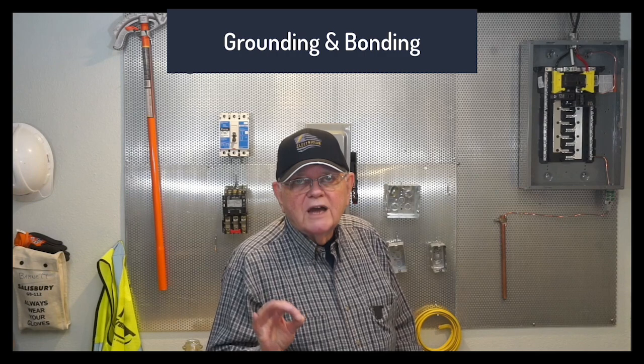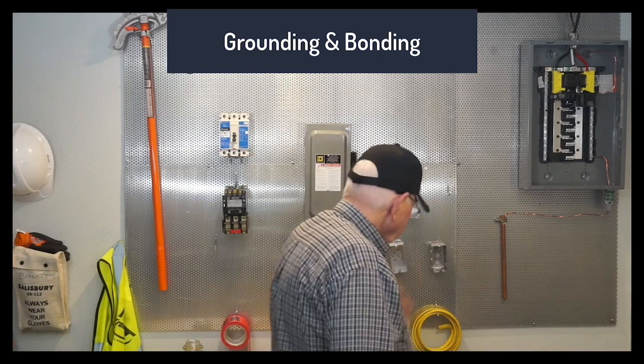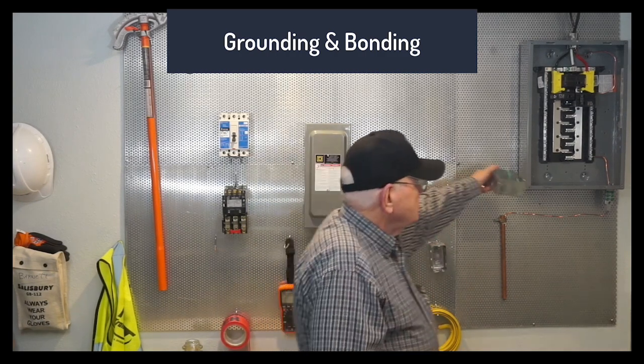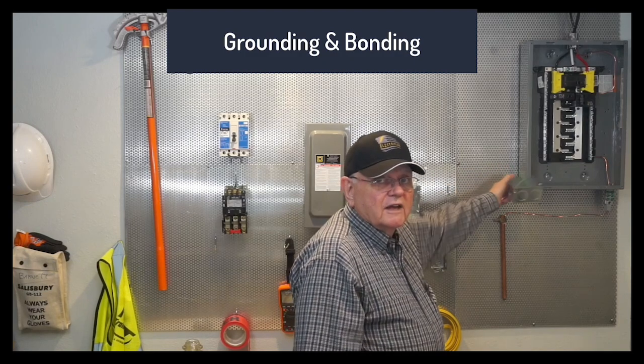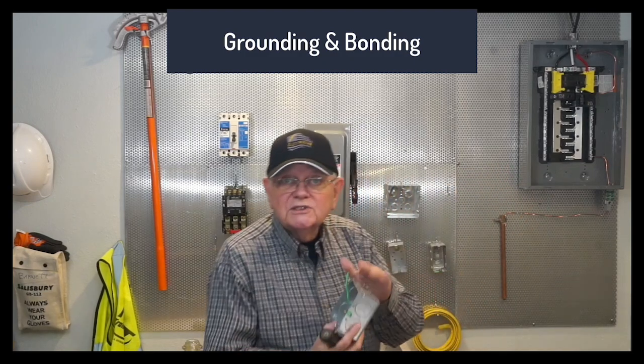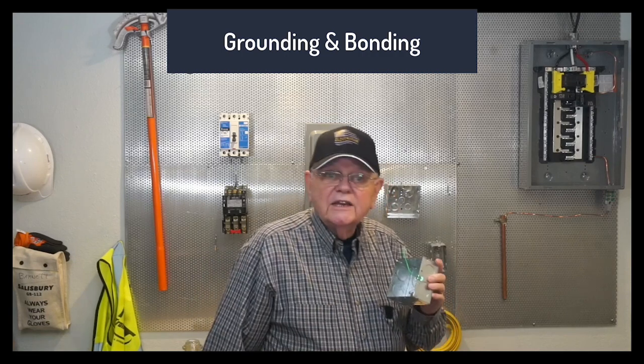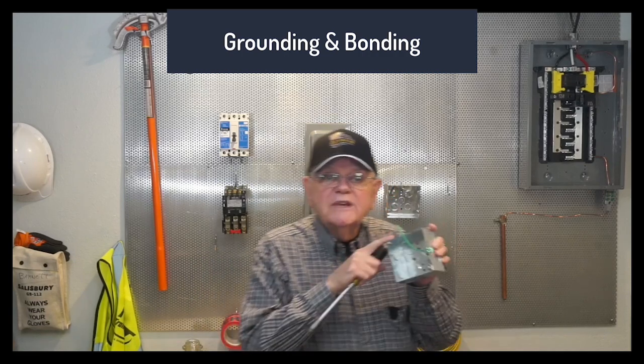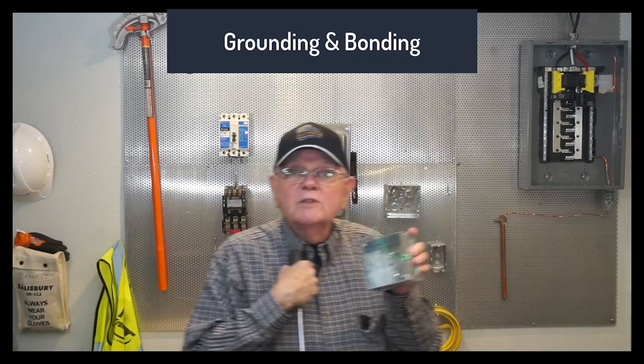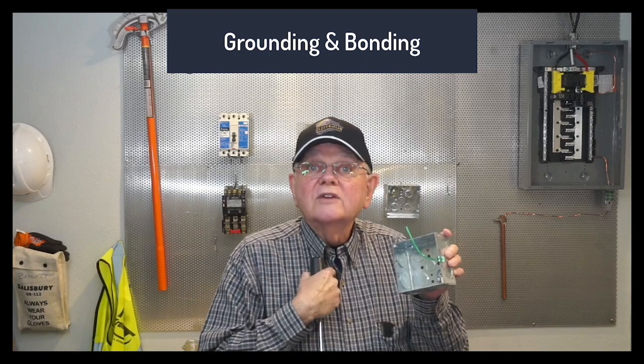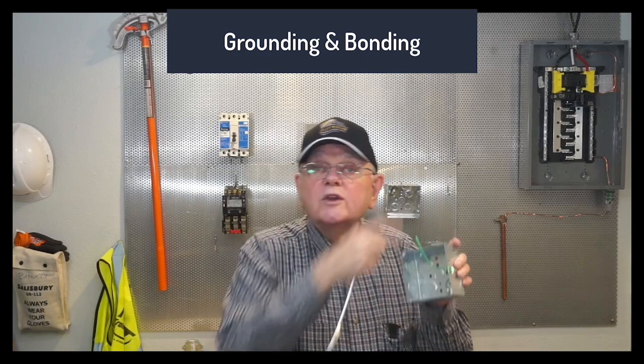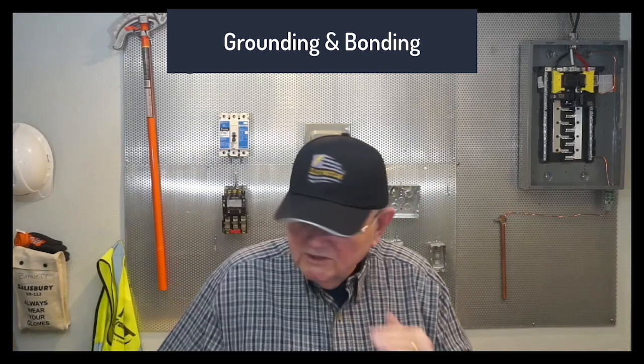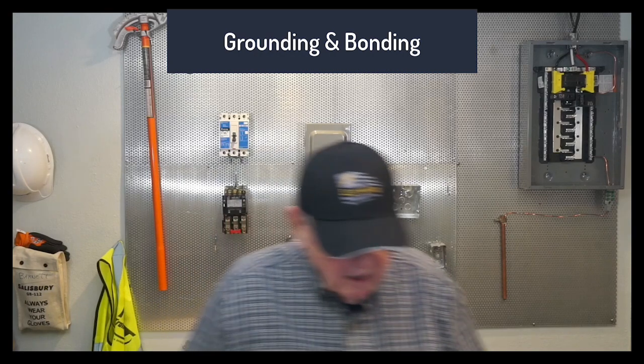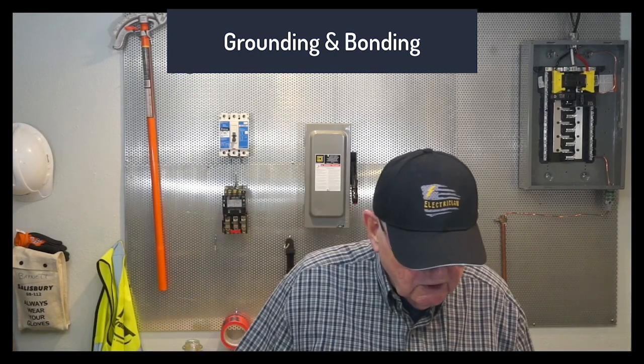Also, what that bonding does, by connecting this box to ground, what have I done? I put this box at the same potential as what I'm standing on. So if the box should become energized, the box and me are both at the same potential. I don't get a shock. I like that idea. And then the breaker trips and clears the fault for me. So just some differences there on grounding and bonding. Always seems to be a point of confusion.